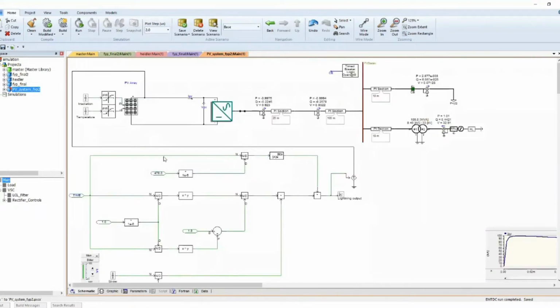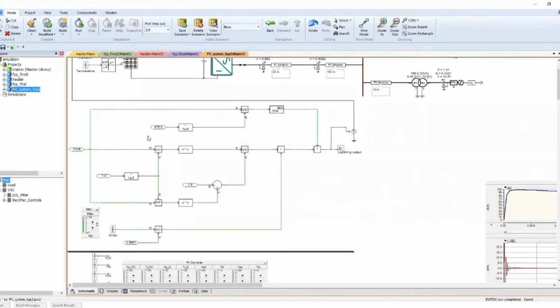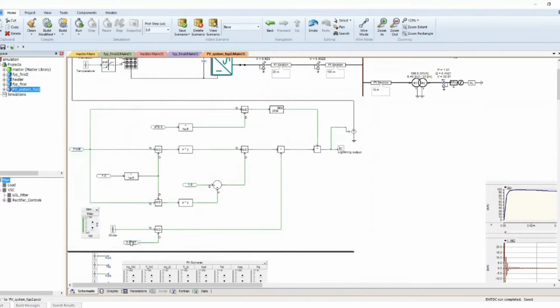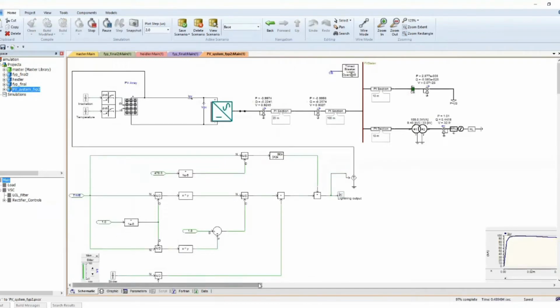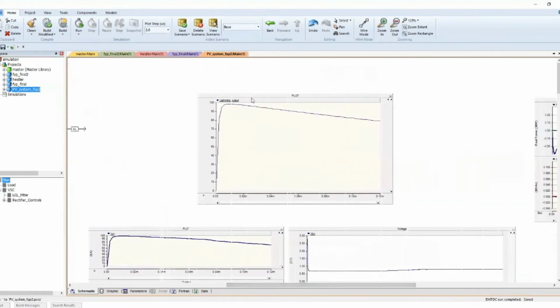So the first simulation is a lightning strike into the PV system with a lightning current waveform of 10/350 microsecond. These are the constants that need to be added. The current is 100 kiloampere. This is the lightning output of the 10/350 microsecond waveform.